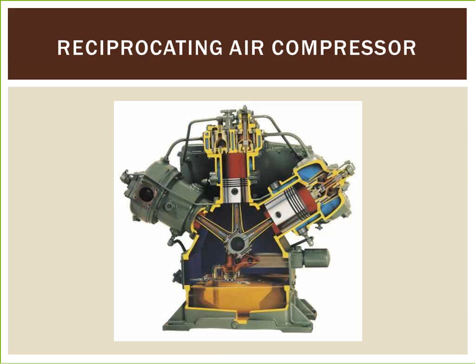The actual compressor section of a system pulls air in from atmosphere and compresses it to create higher pressure air. The three basic types of air compressors are reciprocating, rotary screw, and rotary centrifugal. These types are further specified by the number of compression stages, the cooling method, either air, water, or oil, the drive method, either motor, engine, steam, or some other, and also the lubrication, oil or oil-free, where oil-free means no lubricating oil contacting the compressed air.